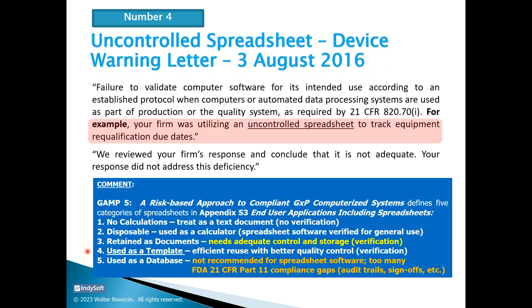GAMP 5 talks about a category used as a template - I'll get back to that. And number five, they identify where predominantly the risk is for organizations. And believe it or not, even in Medtronic, a Fortune 500 company, the largest medical device manufacturer in the world, I saw parts of our business that were still trying to use a spreadsheet when they should have been using a database. They tried to rationalize it from the fact they didn't have many things they were controlling, or it was simple things they were controlling, like due dates. But nonetheless, the FDA and GAMP 5 recommend that you do not use a spreadsheet when a database is the appropriate resource.